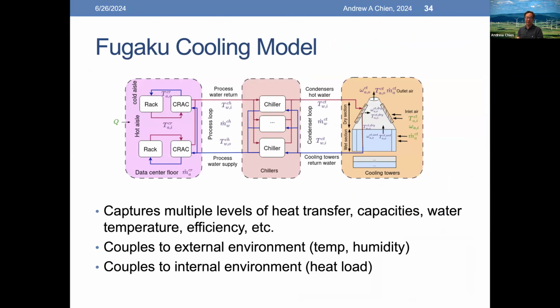So to explore this, we've been building a detailed cooling model for the Fugaku system, and I won't go through this in any kind of detail, but the idea is that there's multiple loops of chilled water and air and chillers and heat transfer to the external world. This model is not engineering complete, but it's complete from a modeling of capacity point of view. And this allows us to capture multiple levels of heat transfer capacities, water temperature, efficiency, and so on.